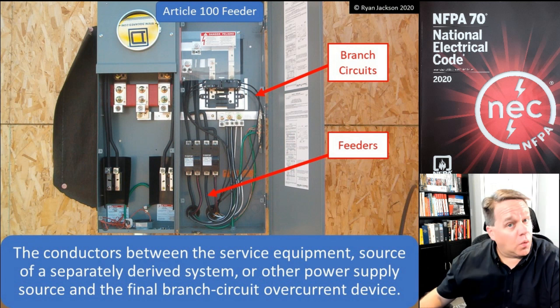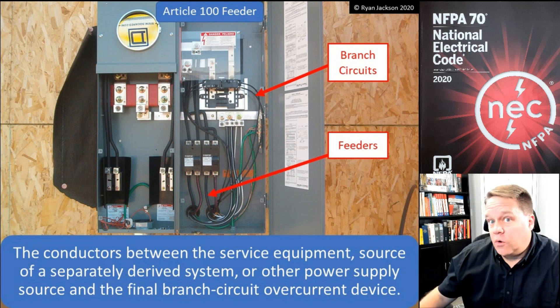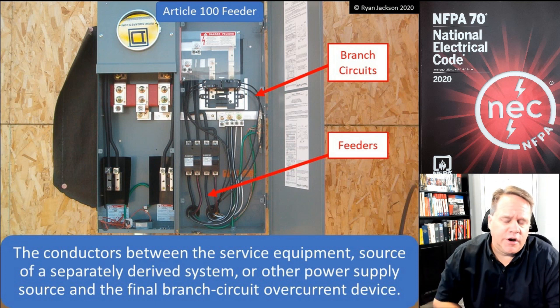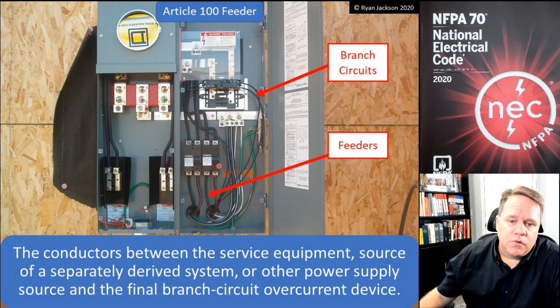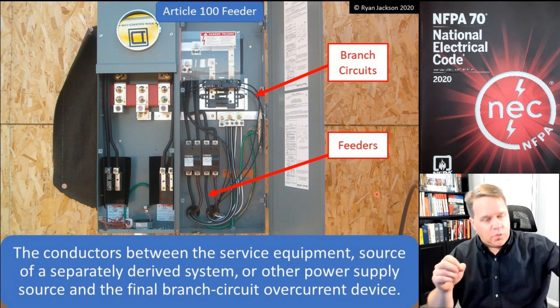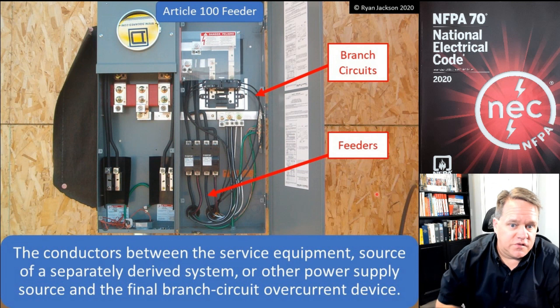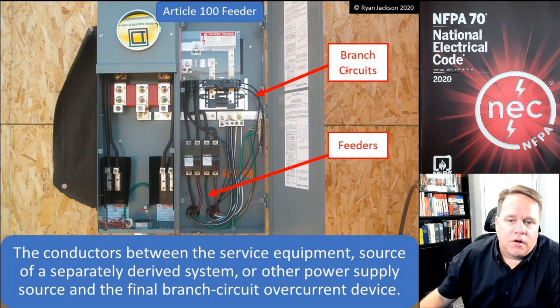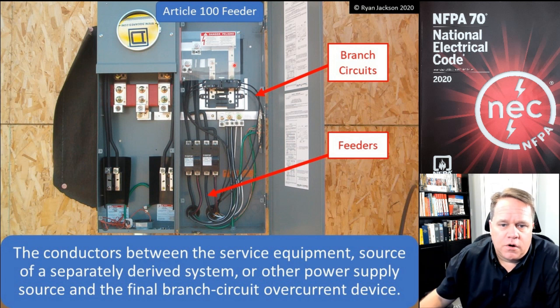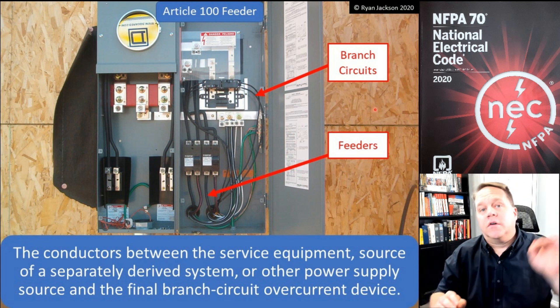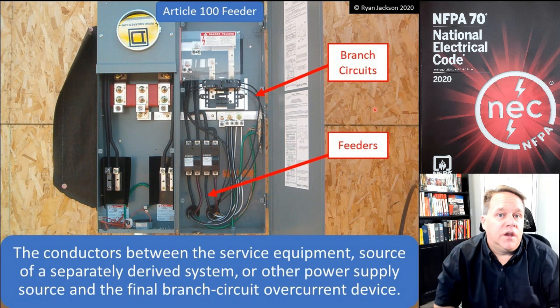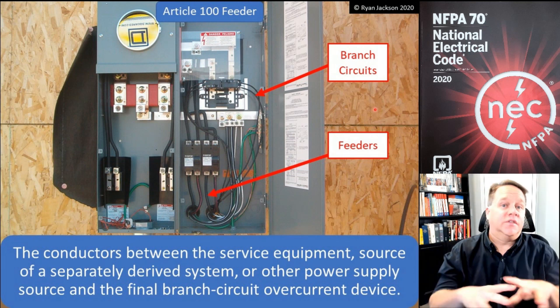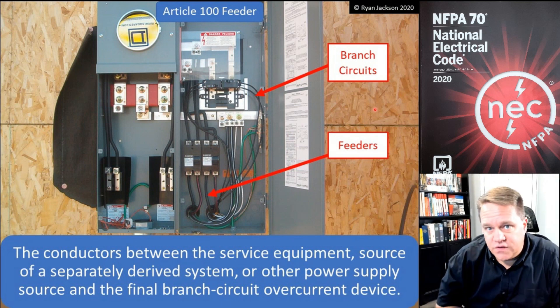Feeder conductors run from the service equipment — or the source of a separately derived system or other power supply source — to the final branch circuit overcurrent devices. In this picture, we've got what's probably a 400-amp service with two 200-amp breakers supplying 200-amp panels in a house — maybe one in the basement and one upstairs. Those are feeders: they start at those two breakers and end at those two panels. Over on the right, we've got branch circuits — maybe a two-pole 30 and a two-pole 40 going to two air conditioners, right out of the breaker into the disconnect and then the AC units.